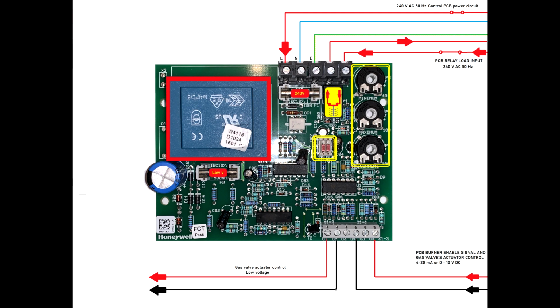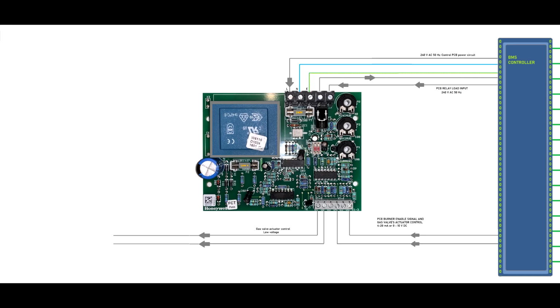Otherwise, you also have towards the middle of the PC board two dip switches that will allow you to set up this printed circuit board to run on 4 to 20 milliamps or 0 to 10 volts. This is simple as such. Now going further, let's see how this can be integrated.